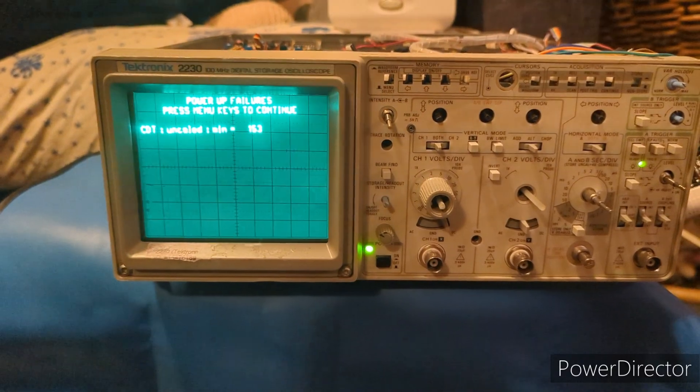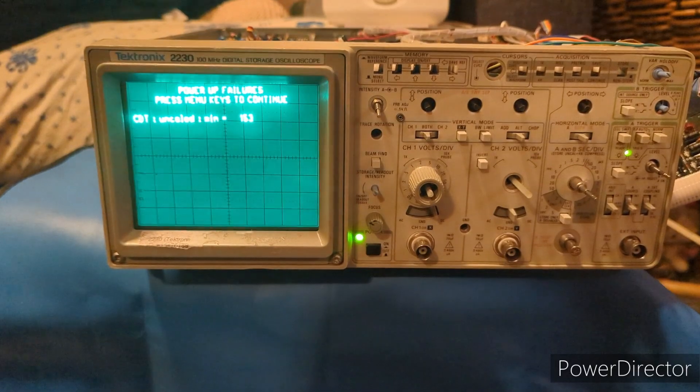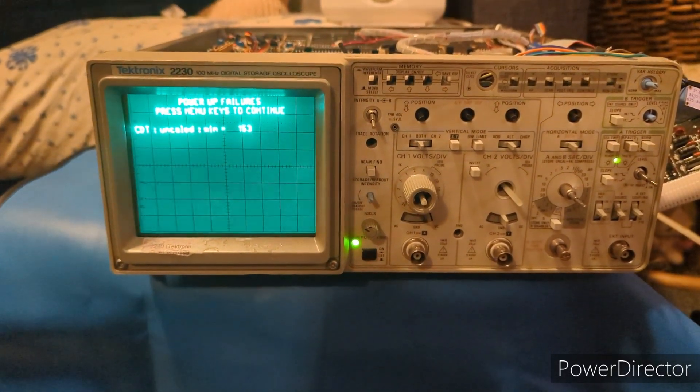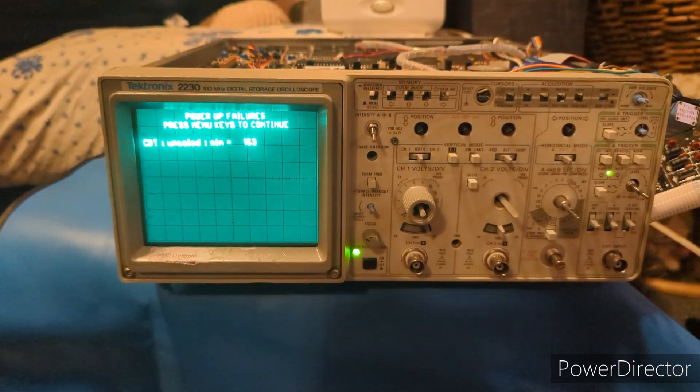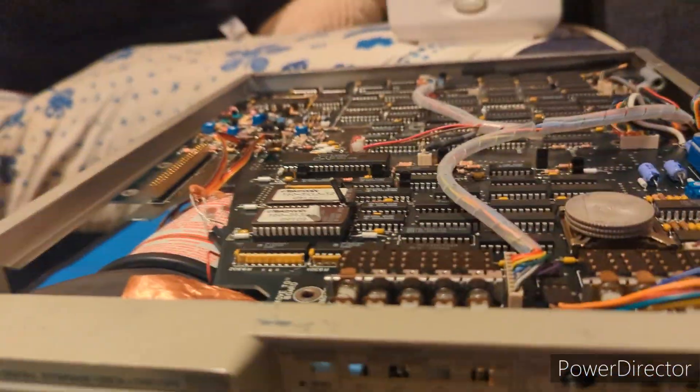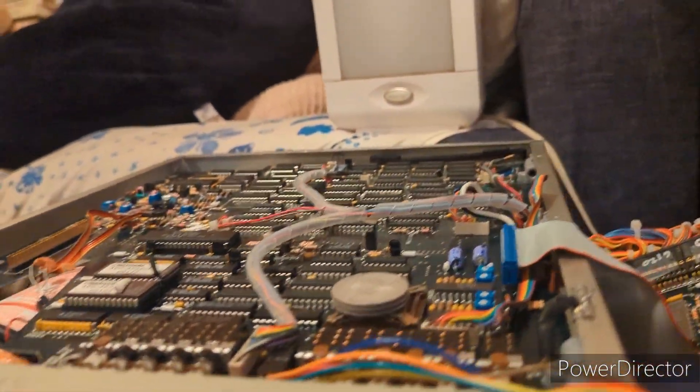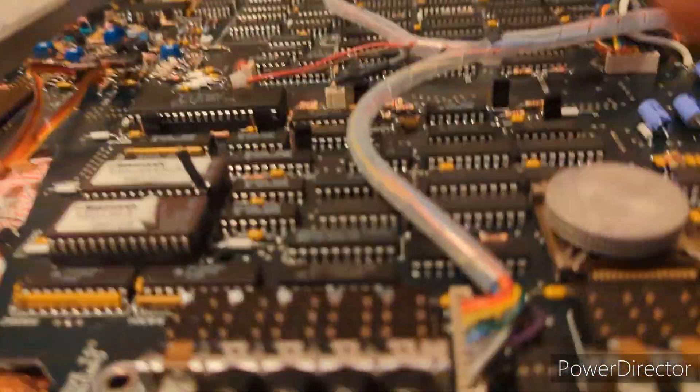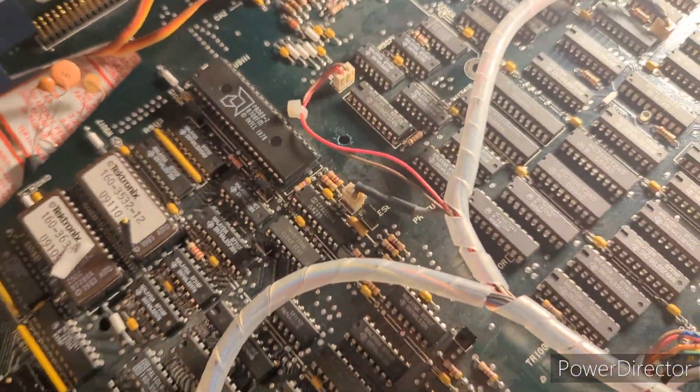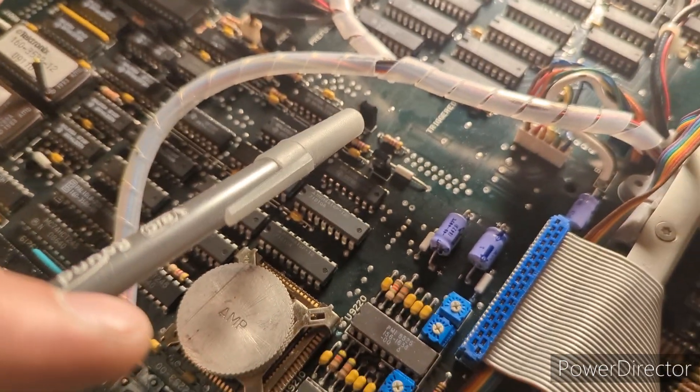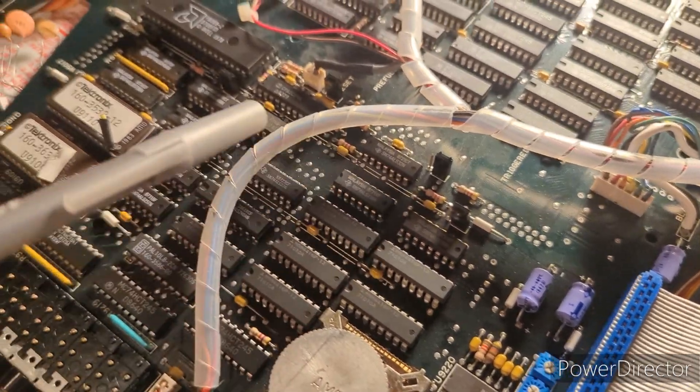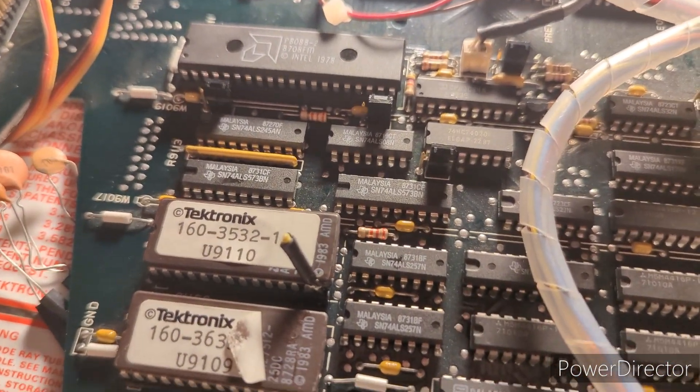See what I could find, see if I could find this fault. Man, I was really struggling. I started with isolating the kernel, which is provided in a procedure in the service manual. You just remove a few of these jumpers. See these black boxes? Let me get a pen. You see these jumpers here? These are little jumpers that you can move over to another position and it'll change the configuration of the digital side.